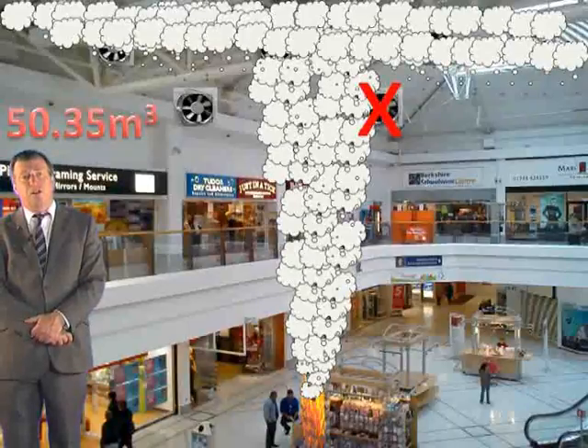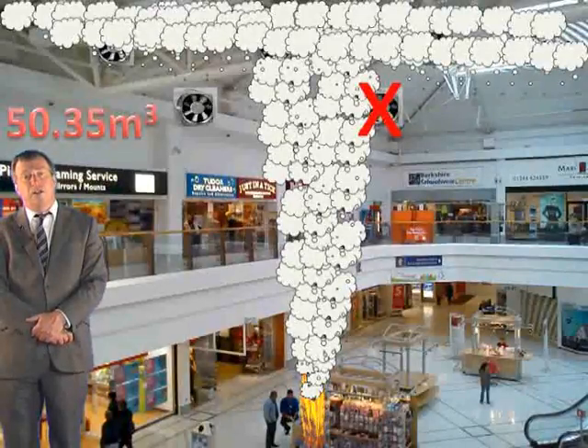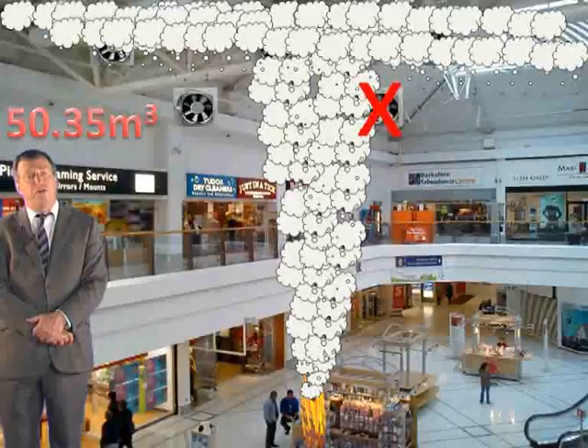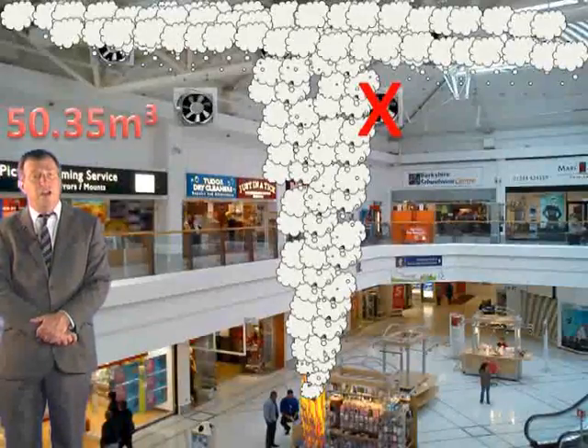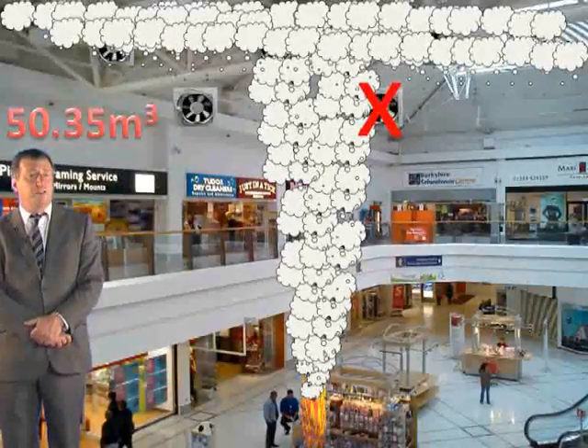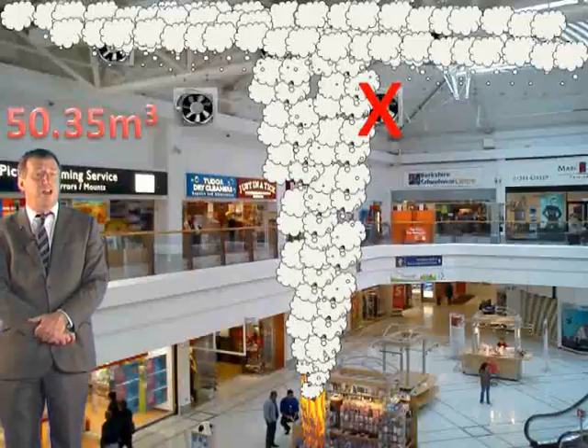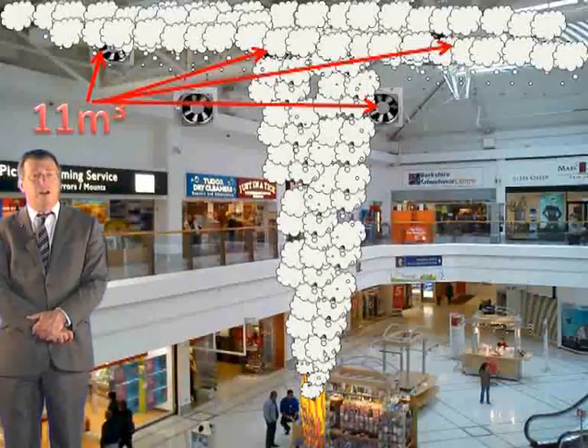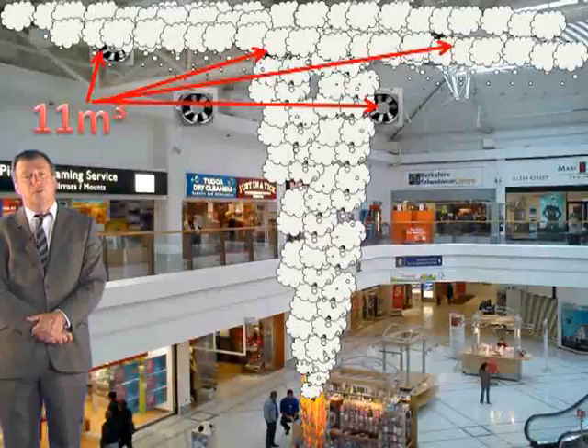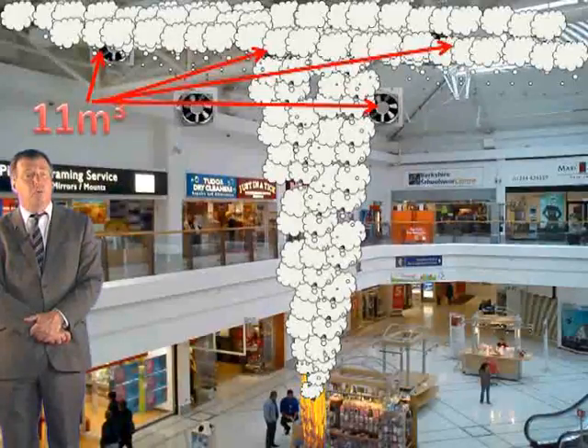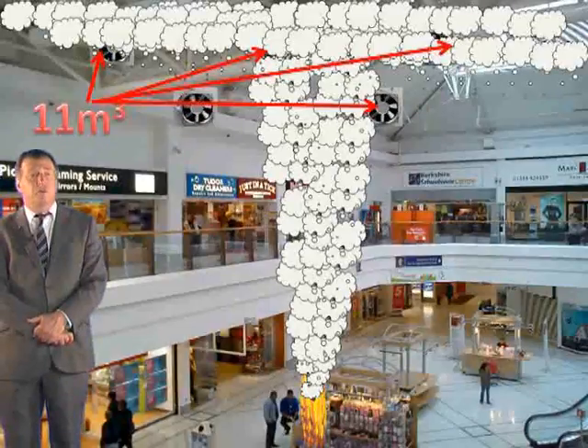So let's suppose, for example, that we have calculated that there will be up to 50.35 cubic meters per second of smoke entering the smoke layer, and that our designer wants to use fans with a capacity of 11 cubic meters per second. Let's further suppose that the distance between the fire loading and the fans is small enough to mean that we might lose one of the fans to the fire. How many fans do we need?